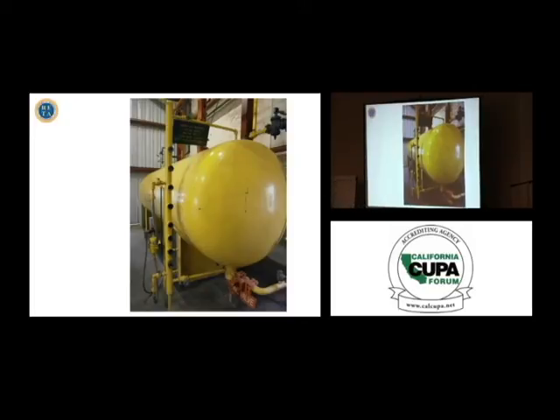To change bearings on it. Long story short, he was killed. Did not do an appropriate pump out. The responding engine company, the state police, the Department of Homeland Security all responded to this particular incident. It was only 106 degrees in South Carolina, but they had closed every valve they possibly could. The contractor took more than 2 hours to go through the gauntlet of security checkup and proving his credentials.